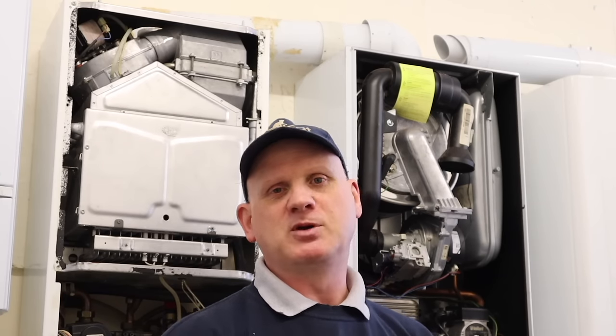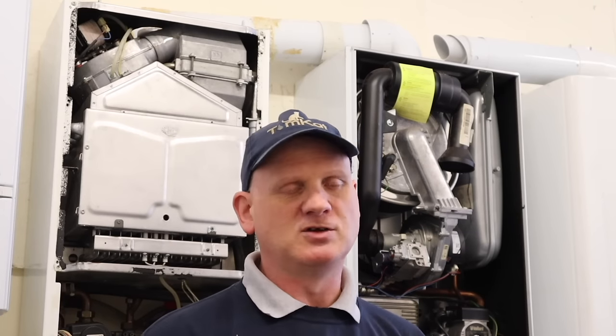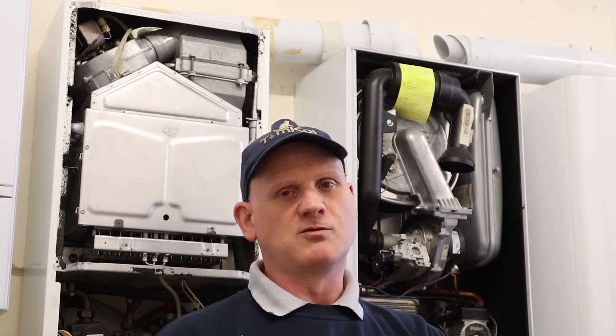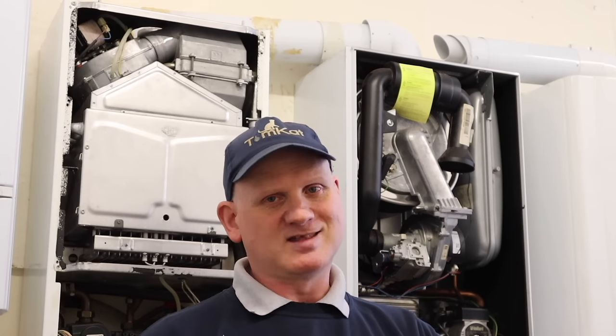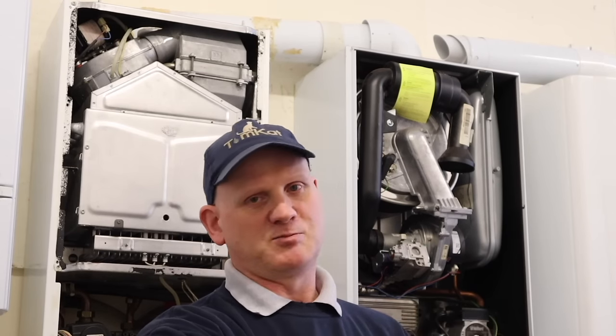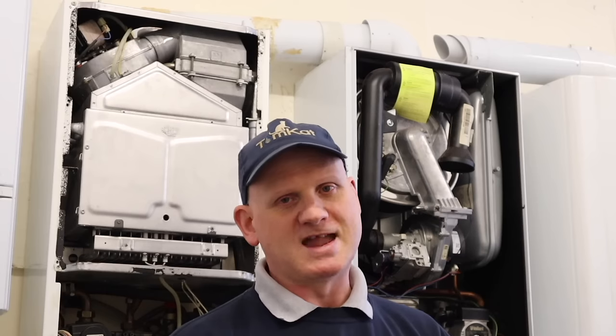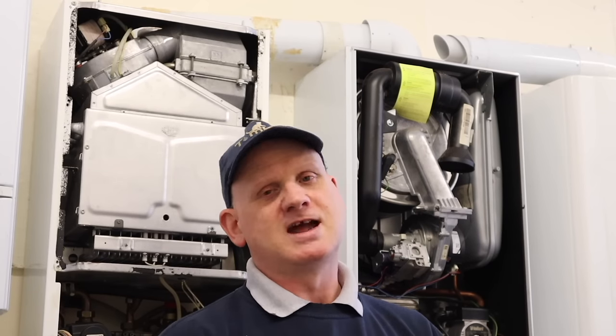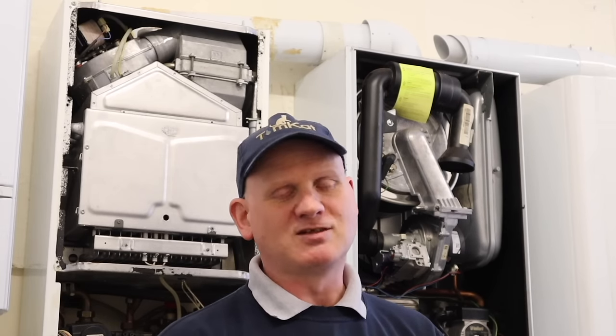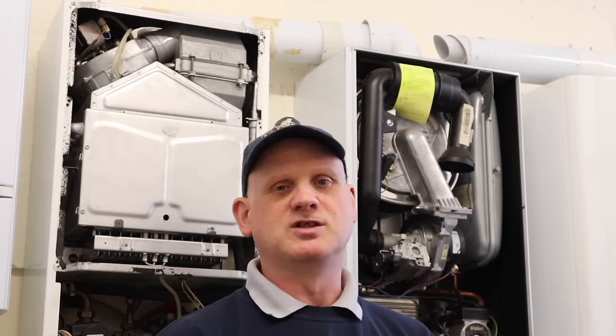So that's what happened with boilers in 2007. We had to have this crossover where we got rid of the non-condensing for condensing, and we got rid of the band B to band A boilers. So all boilers now are band A boilers. They're all condensing and they all have to be more than 93% efficient now to comply with the new regulation.